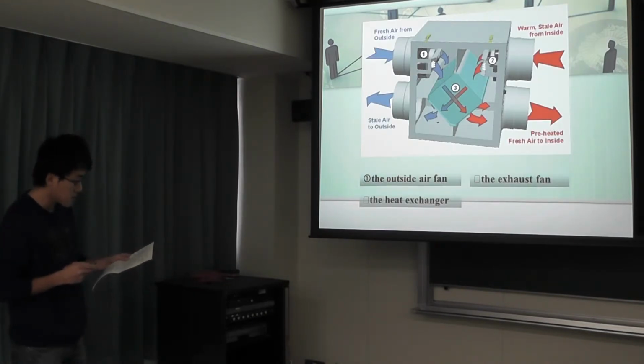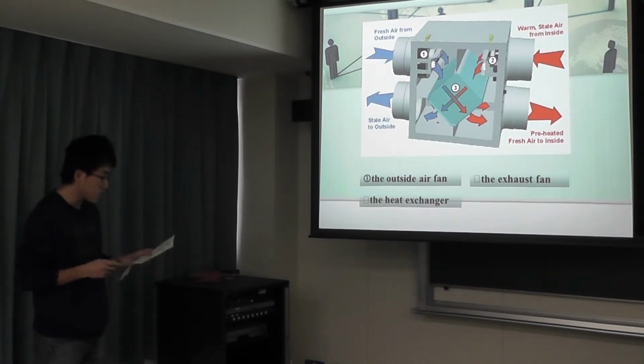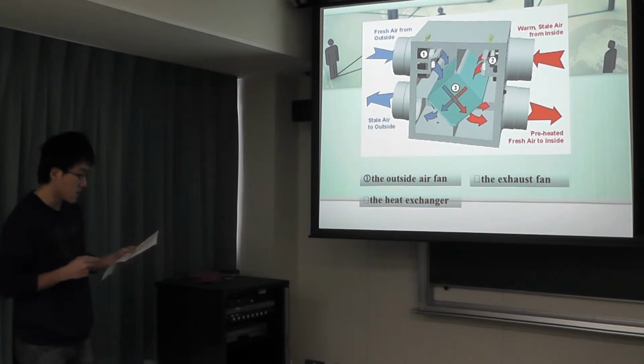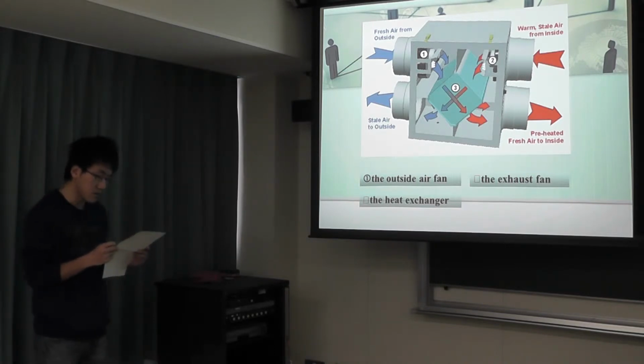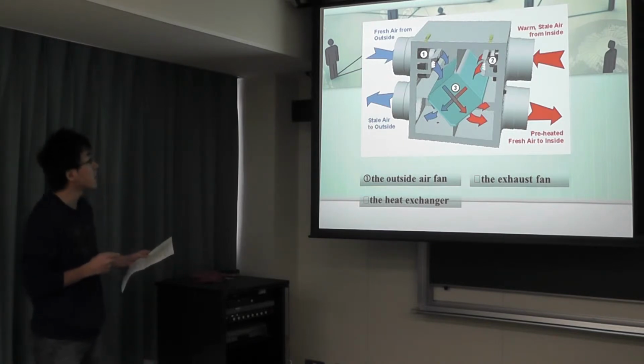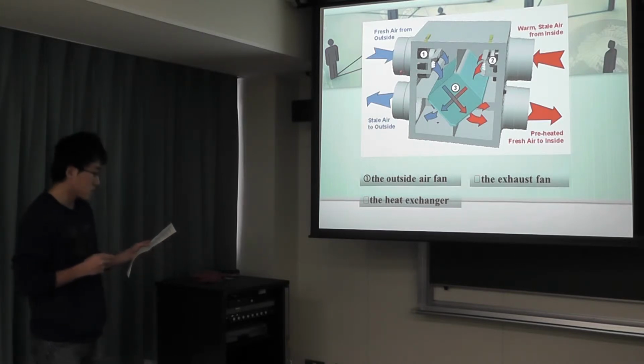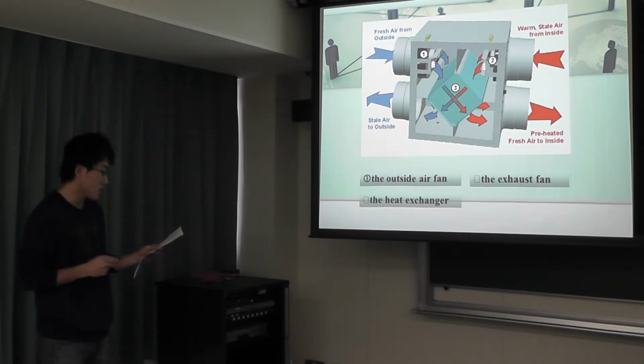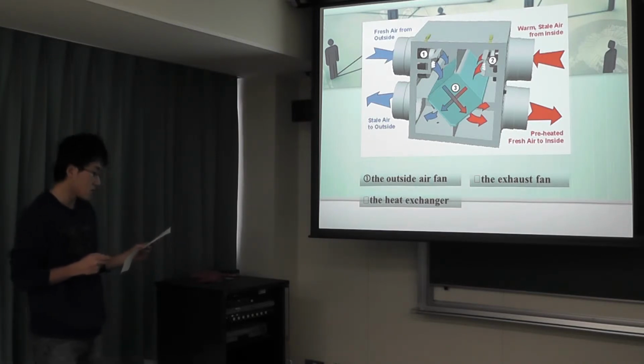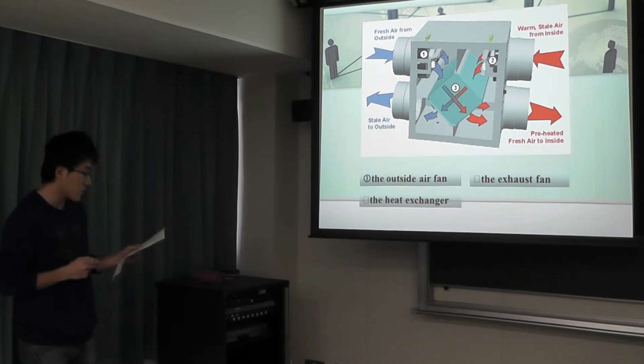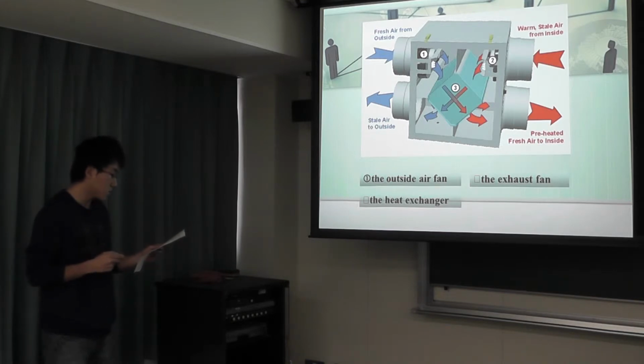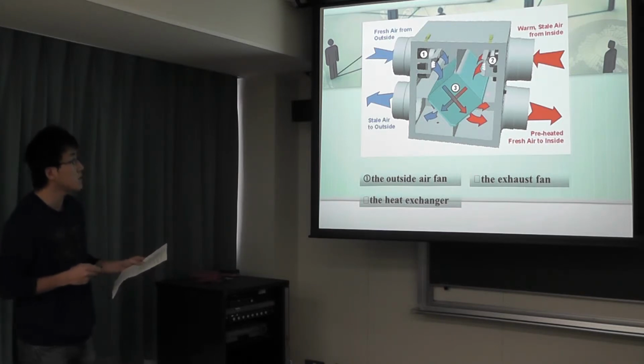This picture shows how the ERV works. The ERV has two fans in the cabinet along with the heat exchanger and a desiccant. The outside air fan 1 draws air in from the outdoors. The exhaust fan 2 draws air in from the home, and the heat exchanger 3 heats or cools the incoming outside air, while the desiccant removes humidity.